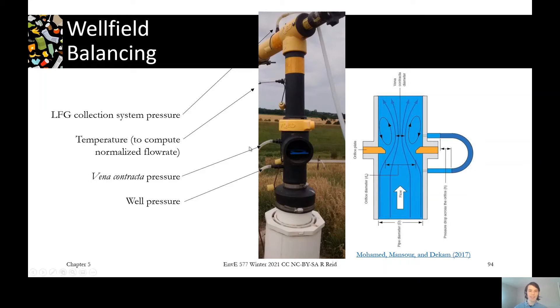So you might have a second port on the other side of this orifice plate and then by measuring between those two, you can calculate the velocity and then the flow rate. So you can actually measure both the pressure and the flow rate with no moving parts with this kind of arrangement. We also have a place for temperature to be measured. So we want to actually be able to normalize that flow rate we calculated to standard so that we can compare it with other wells.